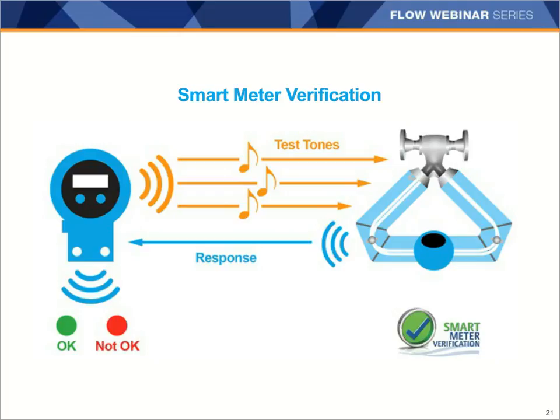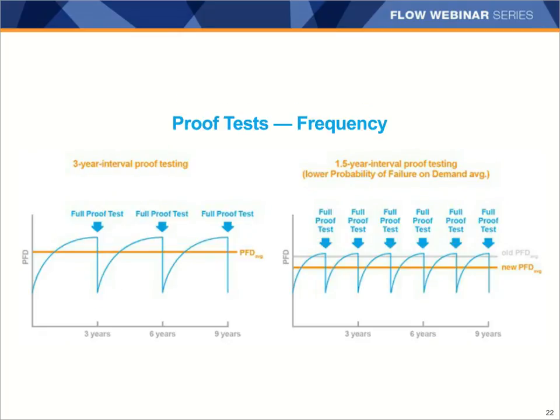And so what I mean by that is, over time, the probability of failure on demand increases if you're not testing anything. And so periodic proof testing is required in SIS to maintain an average probability of failure on demand. So as shown in the first graph on the left, you can have an instrument like a flow meter that has a proof test interval of every 3 years to maintain a certain average PFD. This means that every 3 years the meter has to be proof tested.